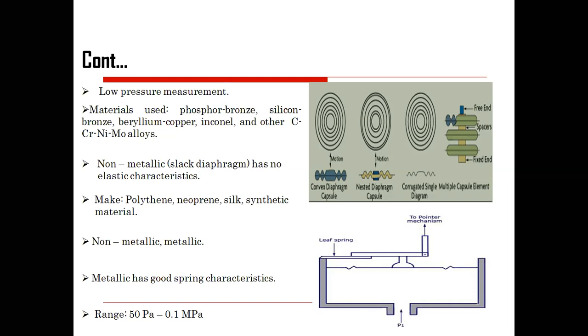Metallic diaphragms have good elastic characteristics that feasibly generate output in response to pressure input. Non-metallic materials like polythene, neoprene, silk, and synthetic materials have minimum elasticity and produce very low output. Metallic diaphragms with good spring characteristics measure pressure in the range of 50 Pascal to 0.1 megapascal.